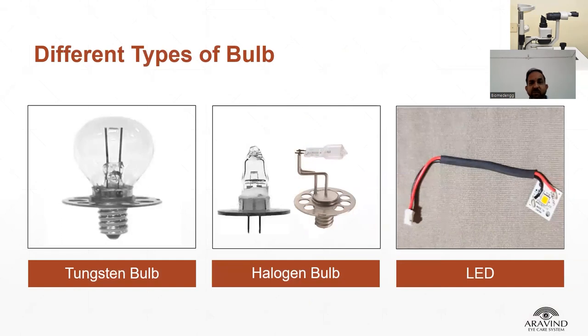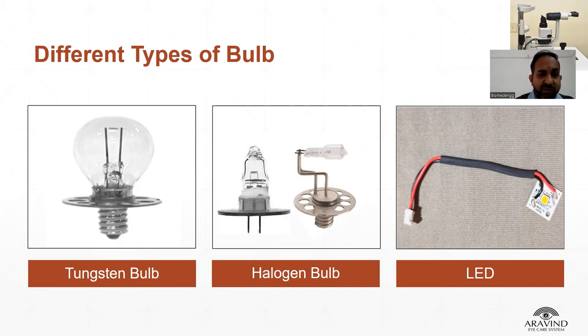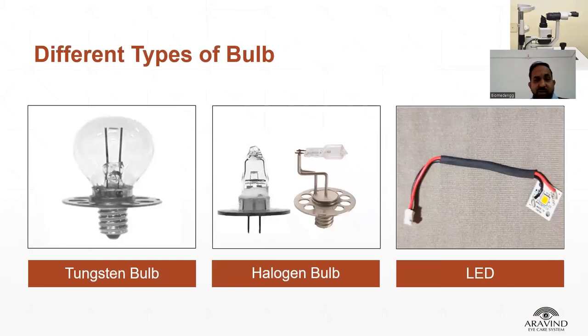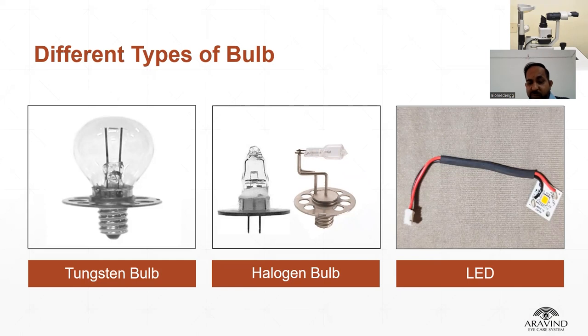Now let's see the different types of bulbs used in the slit lamp. There are basically three types: the tungsten bulb, the halogen bulb, and the LED bulb. The tungsten bulb produces more heat along with light, and its lifetime is around 1,000 hours. Halogen bulbs are slightly brighter than tungsten bulbs, with a lifetime of around 2,000 hours. LED bulbs, recently introduced in slit lamps, have a lifetime of around 40,000 hours and are much cheaper than other types, which is their major advantage.